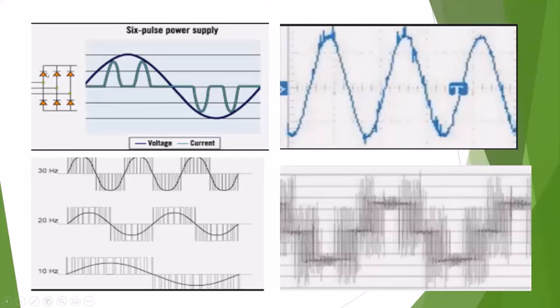So again, this shows the diode front end here, what the pulses are coming in. You can see this is set up as six diodes here, but they do build these out with an extra set of diodes and then bring an extra phase shift in here, and then still bring the power in, but there are many more pulses coming in. So, these resultants are lower. So that's what a 12 pulse is, but it does require an extra phase shift transformer and an extra set of diodes on the front end of the drive.